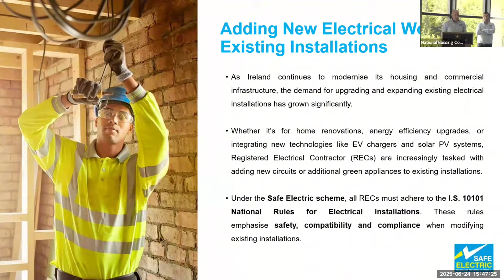Thank you. Hello, everybody. You've been hearing the word rules a lot. So the two key rules with regards to carrying out additional installations to existing installations: part or chapter 1 of the wiring rules, which is the fundamental principles, rule 134.1.9. In the case of an addition or alteration to an existing installation, it shall be determined that the rating and condition of existing equipment which will have to carry an additional load is adequate for its altered circumstances.